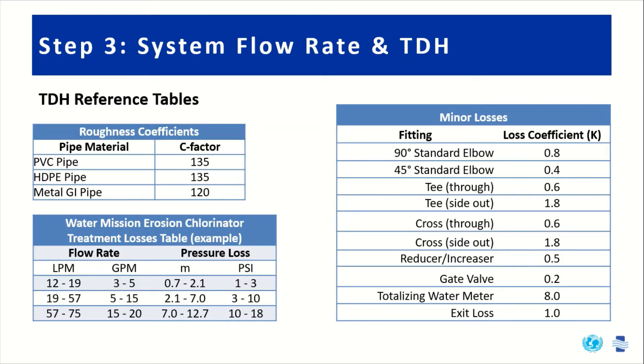These helpful reference tables include factors and coefficients used when calculating TDH. Based on your pipe material, you have different roughness coefficients or C factors, which affect your friction and minor losses. The minor losses table lists various fittings with different loss coefficients. You may also have a table from a manufacturer of water treatment equipment describing the pressure loss through the treatment system.